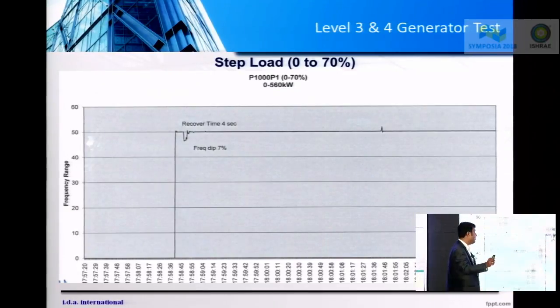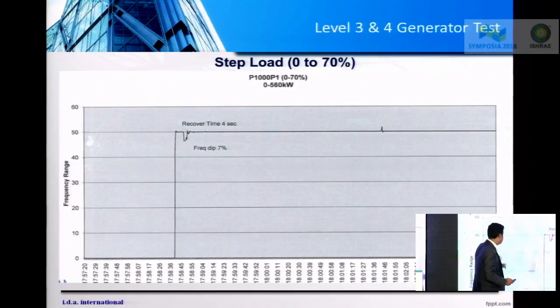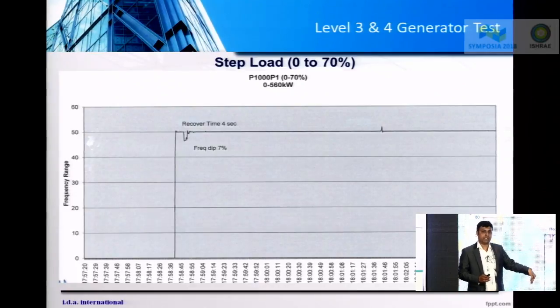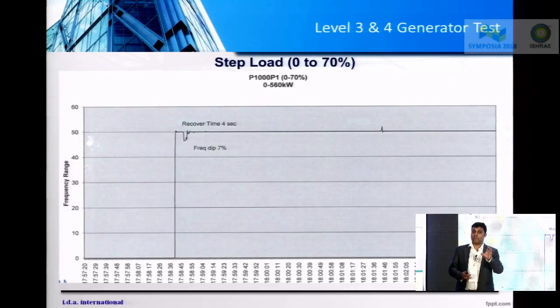So when I am doing a step load test from 0 to 70%, I am verifying the frequency. And you can see here there's a dip in frequency of 7% and the recovery time is 4 seconds. There are certain guidelines laid out by electrical codes that say what the dip in the frequency should be and what the recovery time should be. So this particular test is very important when you're verifying the performance of a generator.